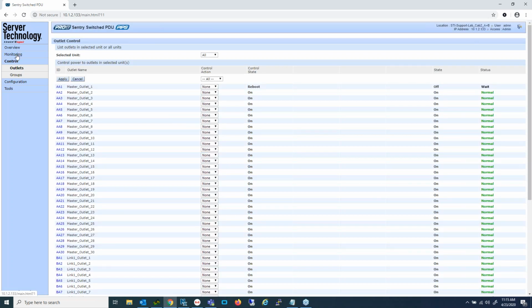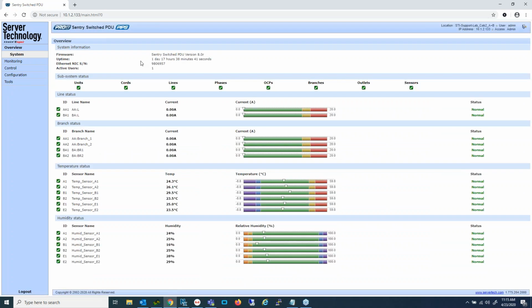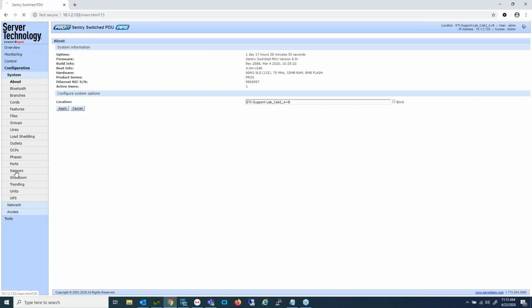If you don't have switch PDUs, if you have smart PDUs, something else you could consider would be to change a threshold, for example for temperature. So I'm going to take a quick look here at current values—we see that temperature is just around 24 degrees Celsius. Let's go ahead and change the threshold for that sensor.